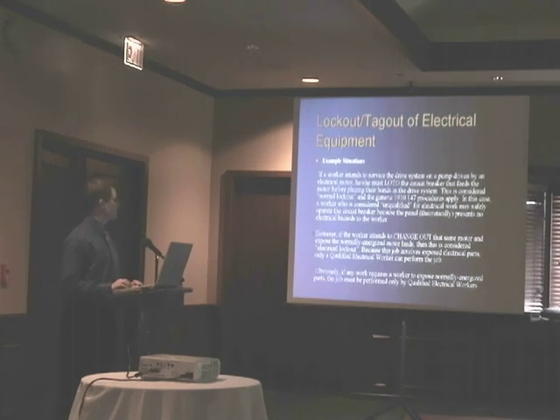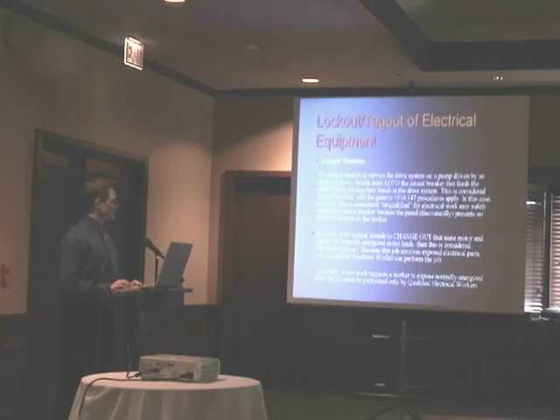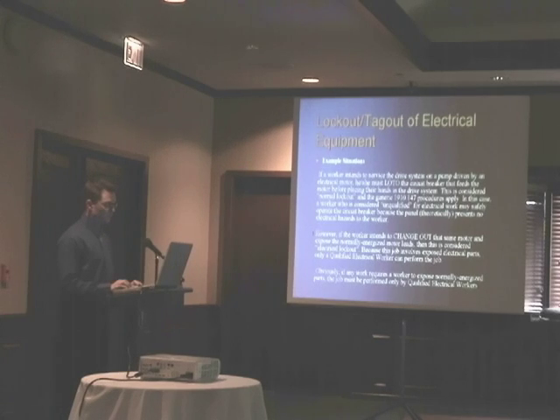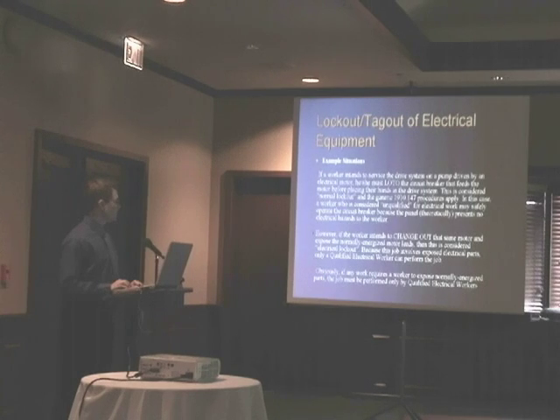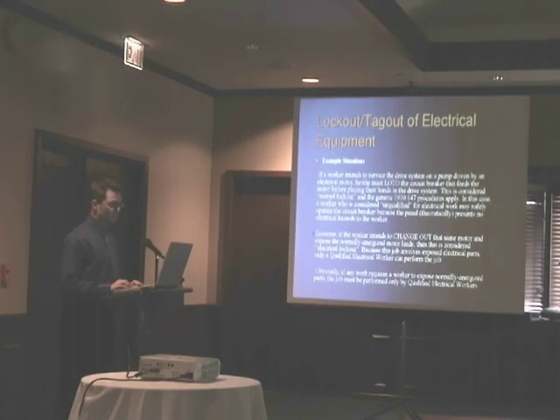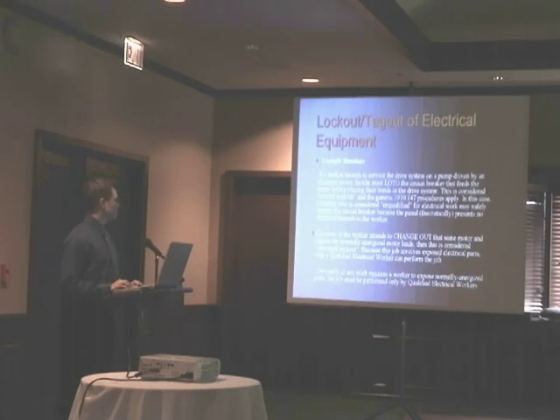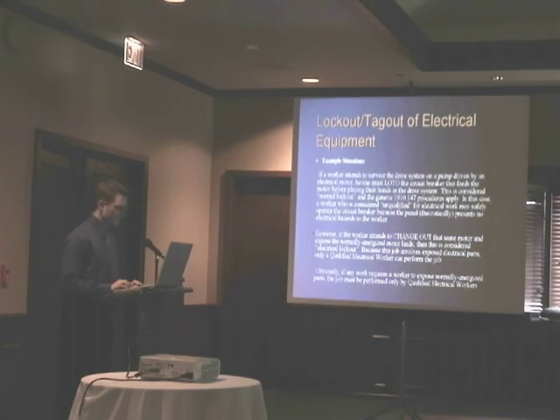Okay, here's an example situation. If a worker intends to service a drive system on a pump driven by an electrical motor, he or she must lock out and tag out the electrical breaker that feeds the motor before placing their hands in the drive system. This is considered normal lockout, and the generic 1910.147 OSHA procedures apply. In this case, a worker who is considered unqualified for electrical work may safely operate a circuit breaker because the panel presents no electrical hazards to the worker.